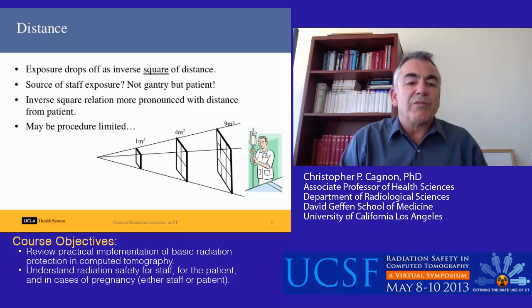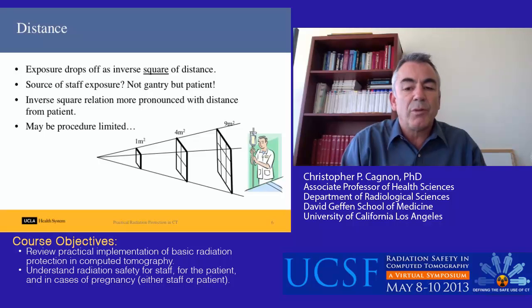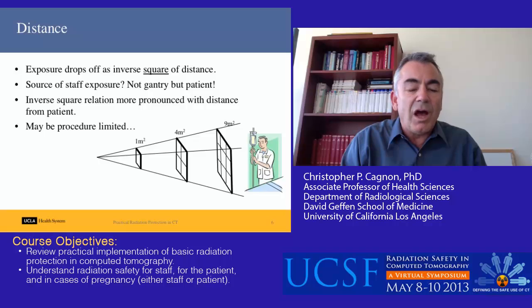Distance — everyone should be familiar with this one. Exposure drops off as the inverse square of the distance. Strictly speaking, this assumes the source of radiation is a point, but in fact the actual source of staff exposure when they're in the scan room is the patient — it's the point where the beam is entering the patient, not the gantry. The greater distance you are from where the beam enters the patient, the more pronounced the inverse square relationship becomes.